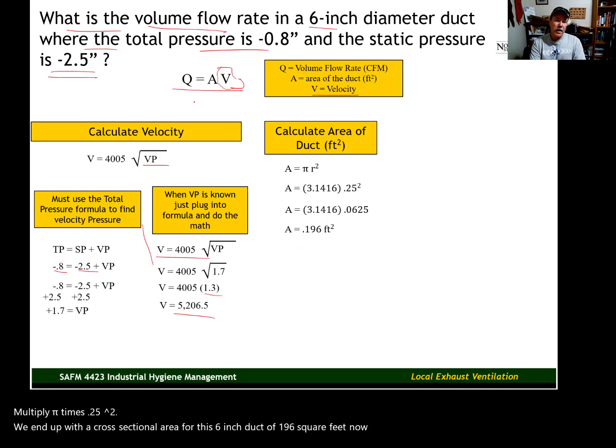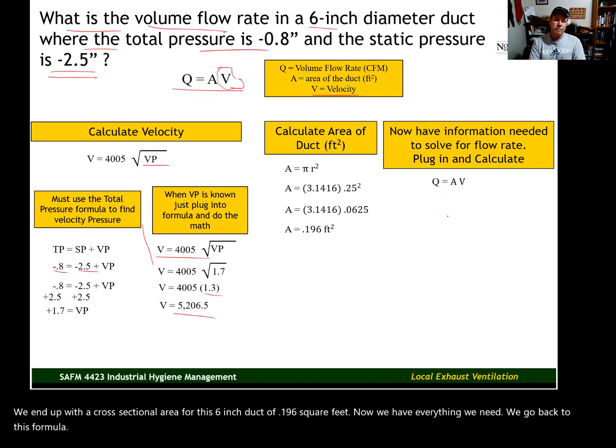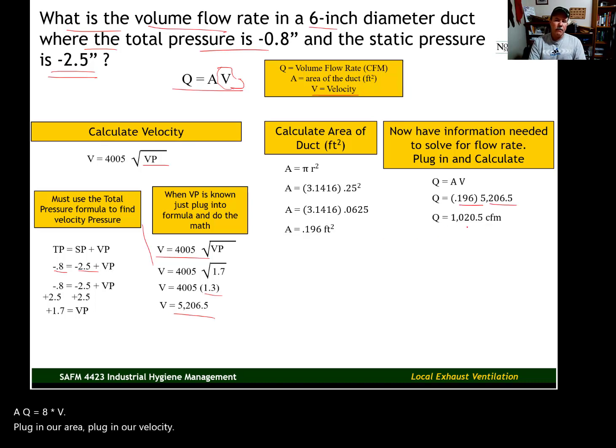Now we have everything we need. We go back to this formula. Q equals A times V. Plug in our area. Plug in our velocity. And we end up with a volume flow rate of 1,020.5 cubic feet per minute.